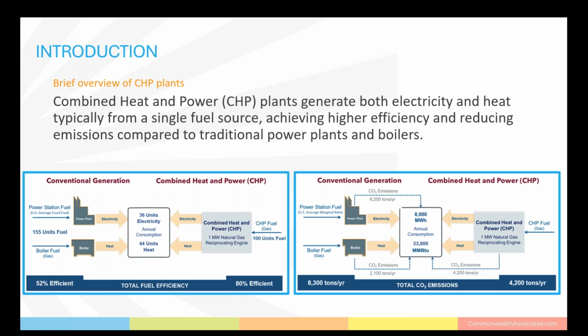As the name denotes, CHPs produce both heat and electricity, usually from a single fuel source. They can achieve higher efficiencies of 65 to 80%, with some systems nearing 90% efficiency, which is significantly higher than the average 52% efficiency from conventional power generation. And based on EPA statistics, the CHP emits 4,200 tons of CO2 per year, while the separate heat and power systems of a conventional plant emit a total of 8,300 tons of CO2 per year.